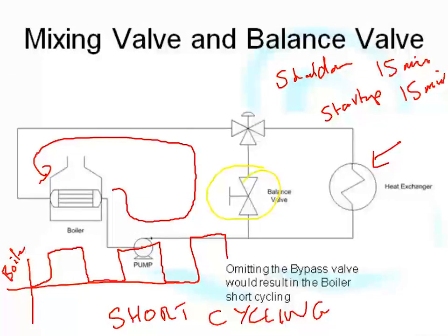In addition to that, boilers are designed to run hot. They're designed to be continuously hot. And if you don't run a boiler hot, then it tends to leak, and water leaks out of it everywhere. And that's not a good thing. The other very bad thing is that most boilers are made out of cast iron, and if you keep heating and cooling and heating and cooling them, you will crack the boiler. And, well, that's quite unpleasant as well, and it's not popular.